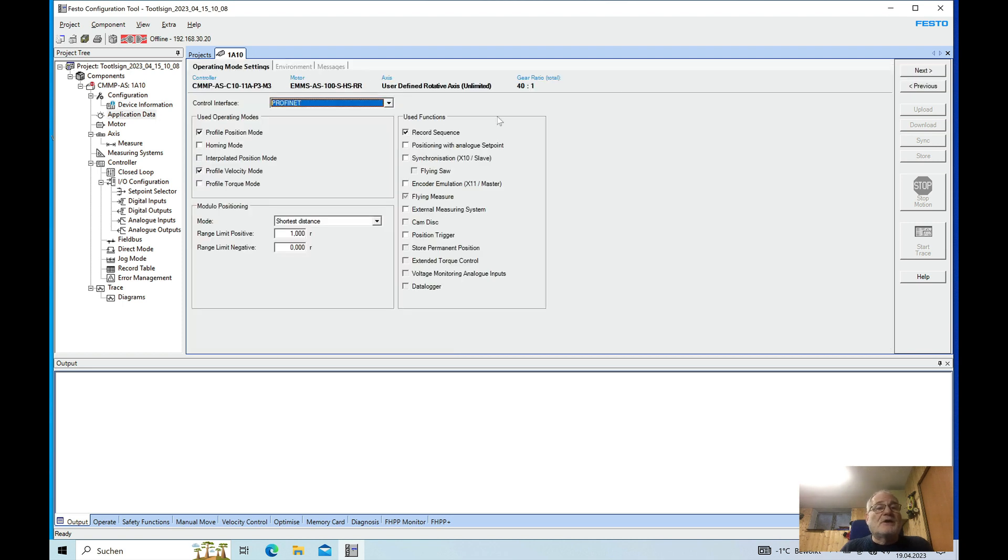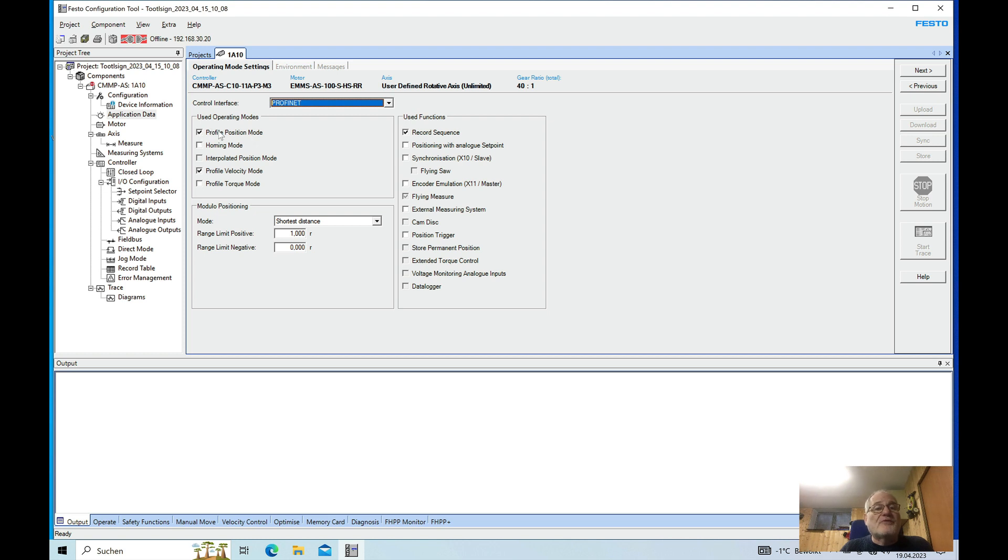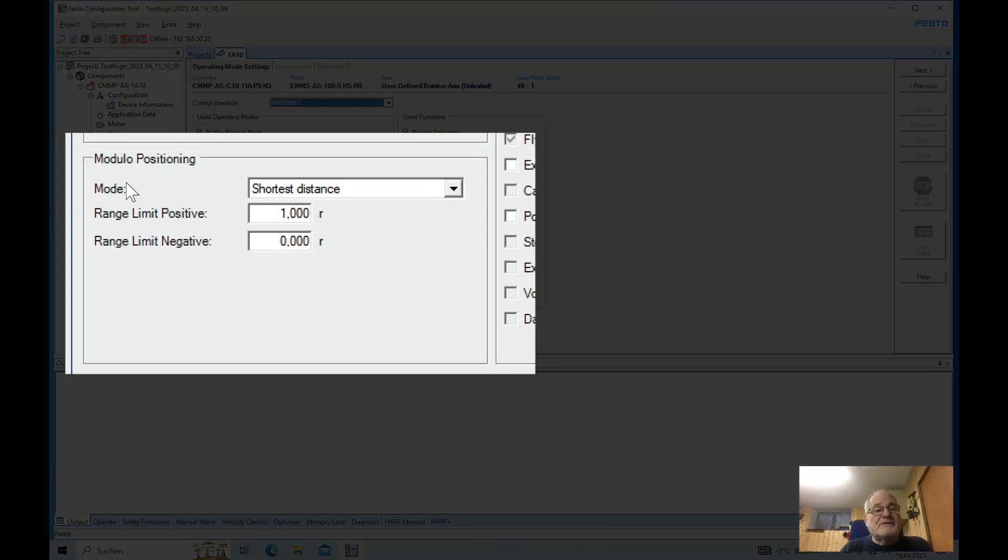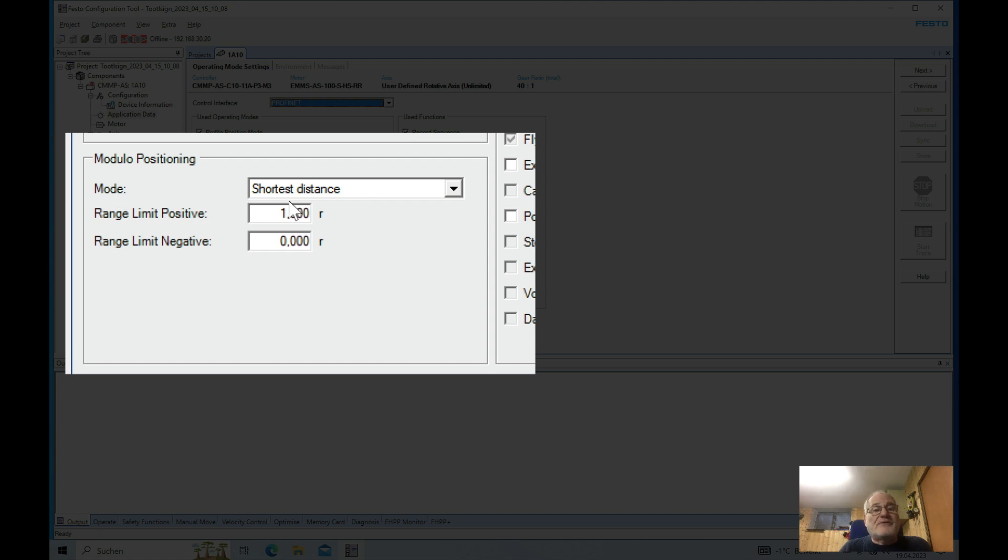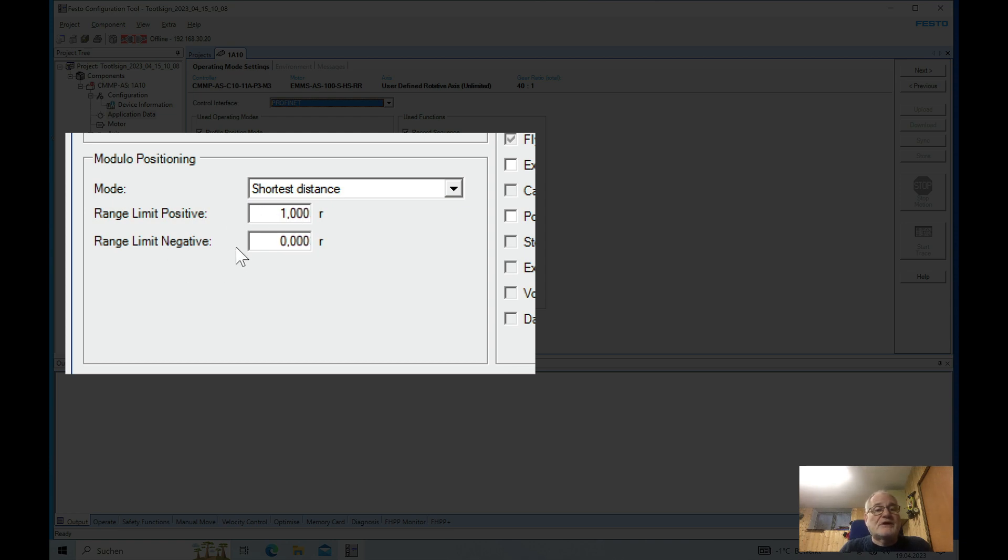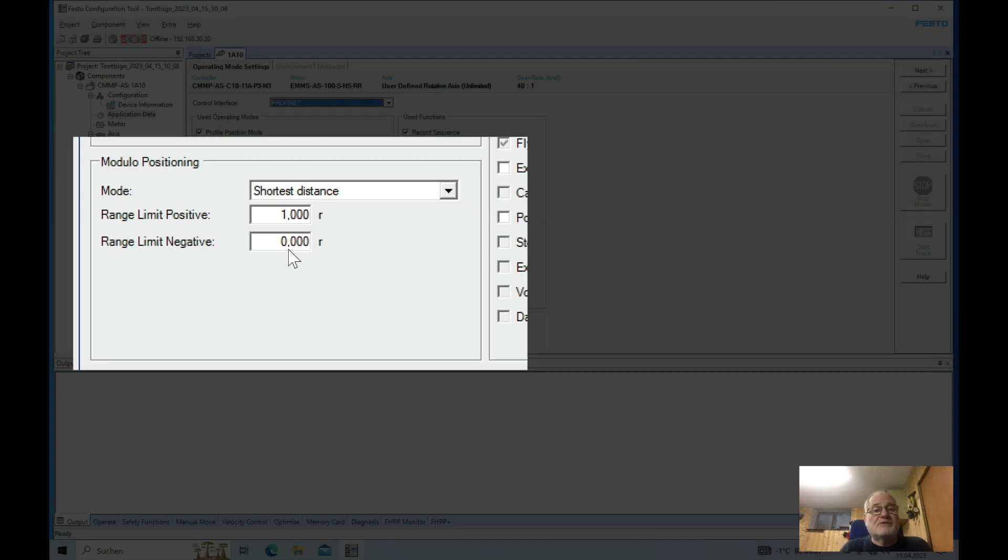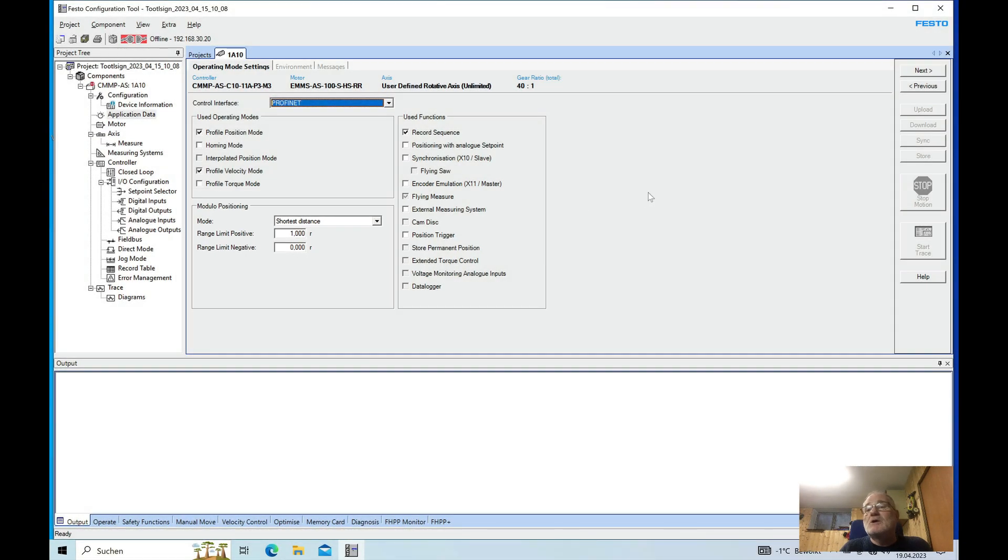On here I have the control interface as a PROFINET and then I do use the profile position mode and the profile velocity mode. And down here in this section the modulo positioning I have set up for the shortest distance using the range limit positive 1 and the range limit negative 0.